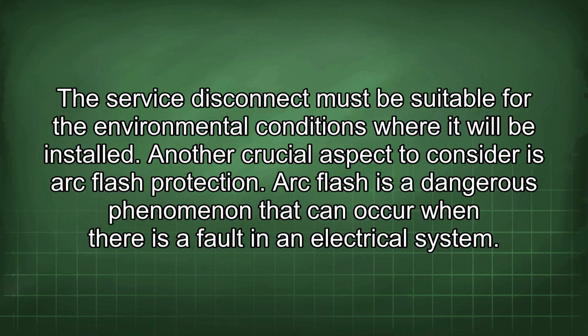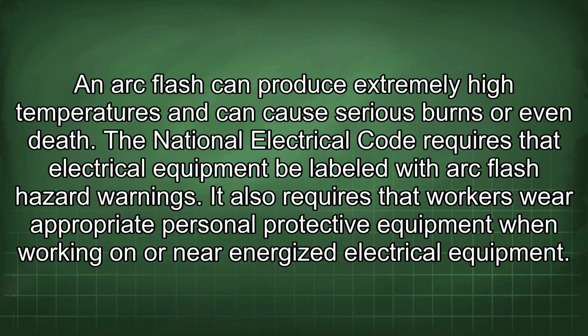Another crucial aspect to consider is arc flash protection. Arc flash is a dangerous phenomenon that can occur when there is a fault in an electrical system. An arc flash can produce extremely high temperatures and can cause serious burns or even death. The National Electrical Code requires that electrical equipment be labeled with arc flash hazard warnings. It also requires that workers wear appropriate personal protective equipment when working on or near energized electrical equipment.